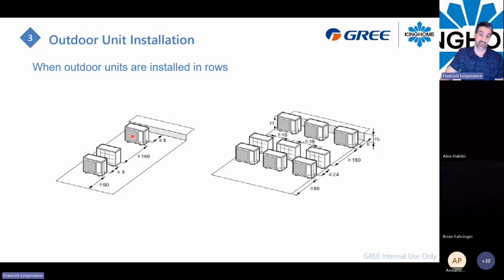We don't want this unit pushing the air through the other one here. So by having 160 inches between those two, they will not push the air into the other coil. If you have multiple rows like this, you will use the same kind of installation. It's a little bit more if you have multiple here, so 24 inches, and maybe you can go as far as 180 between those kinds of units.